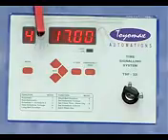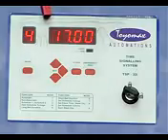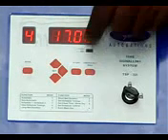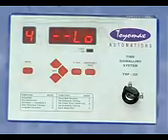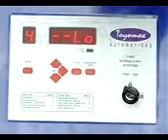Black is connected to the neutral, and green or yellow is connected to the bell output, and the other point of the bell is connected to the neutral. So this is the concept of connecting our timer with your existing bell which has a phase cut and neutral connection.